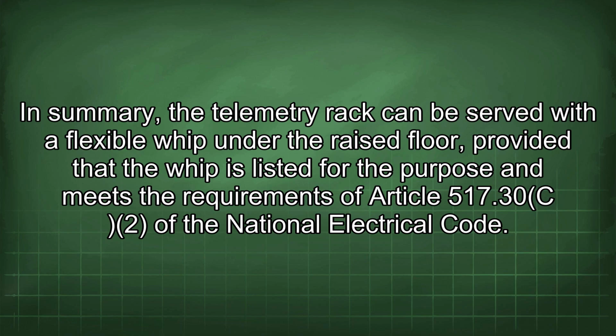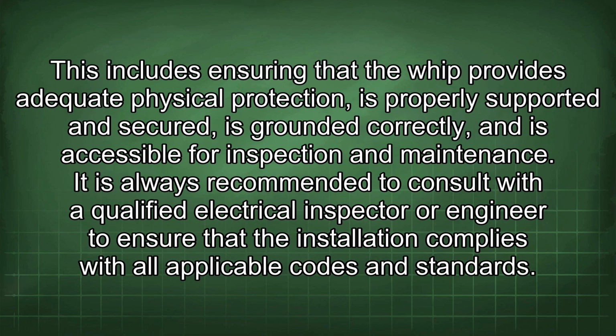access. In summary, the telemetry rack can be served with a flexible whip under the raised floor, provided that the whip is listed for the purpose and meets the requirements of Article 517.30(C)(2) of the National Electrical Code. This includes ensuring that the whip provides adequate physical protection, is properly supported and secured, is grounded correctly, and is accessible for inspection and maintenance. It is always recommended to consult with a qualified electrical inspector or engineer to ensure that the installation complies with all applicable codes and standards.